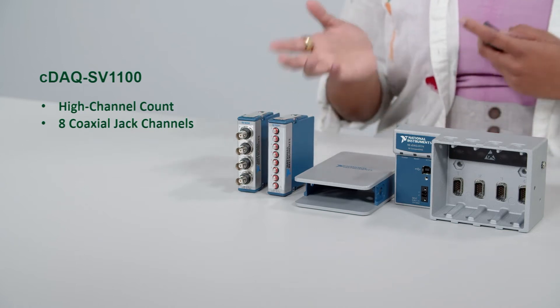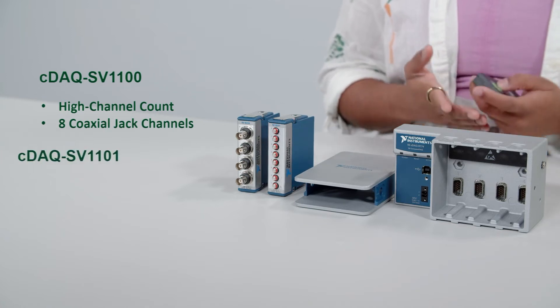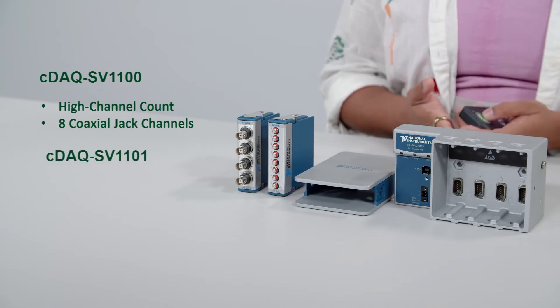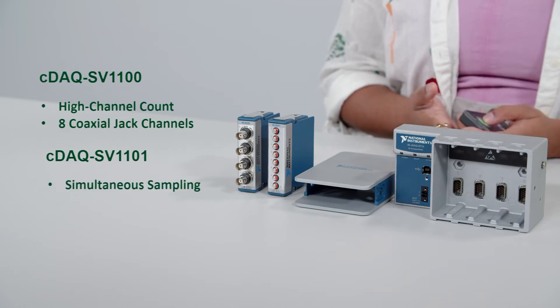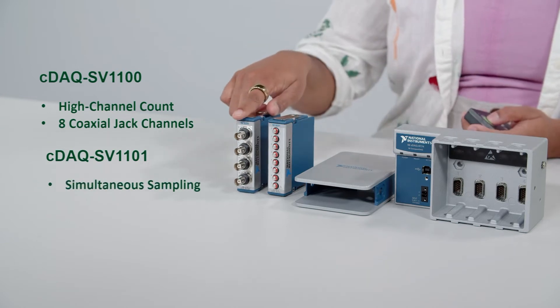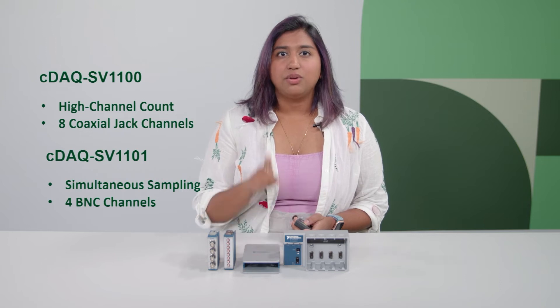But if you need a different sensor connection plus more data points per sensor, then the cDAQ-SV1101 bundle is the one you want to start with. It comes with a module that has simultaneous sampling and can be connected to four BNC connector sensors. As mentioned, both these bundles have a one-slot chassis, so keep in mind you can only have one module connected per test sequence.